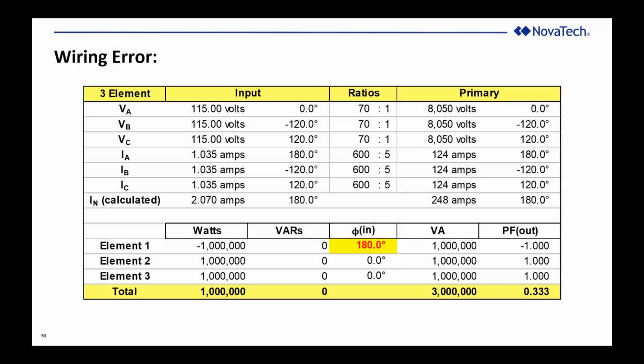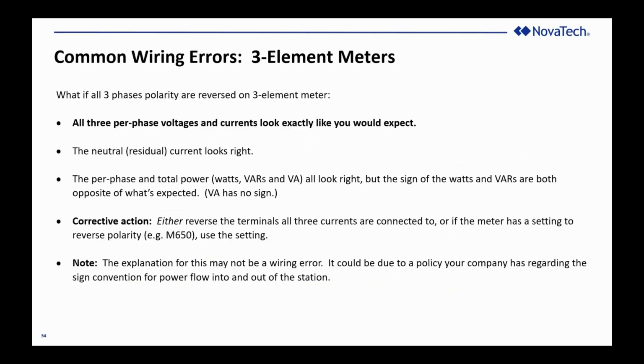This is for comparison, just between having one phase inverted and having two phases inverted. You can flip back and forth and see what the difference is in the calculator. What happens if all three of them are reversed? Okay, all the voltage and current looks normal. The residual current looks normal. Per phase and total watts, VARs, and VA all look right, but the sign of the watts and VARs are both opposite. Corrective action might be to reverse all three phase currents, or the note at the bottom of the page, consult your company policy.